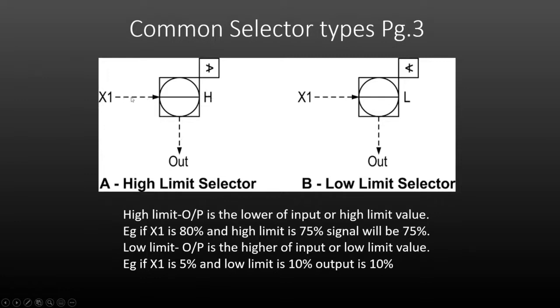For example, if X1 is 80% but we have a high limit set at 75%, our output will be clamped at 75%. Image B shows the inverse — a low limit selector. The output is the higher of the input or the low limit value. So if X1 is 5% and the low limit is 10%, the output is going to be 10%. Both of these have very defined operations.